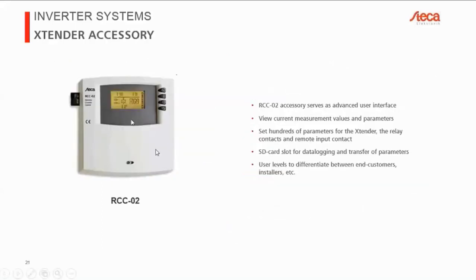So that's what the RCC02 is for. You can already sort of see it on the display. It shows you the current state. It shows you voltages, currents, powers, and temperature, all kinds of things. So you can use that as an advanced user interface. You can see all your current measurement values and parameters. Like I said, there's literally hundreds of parameters you can set on the Xtenders. In practice, you typically only need to set about 5 to 10 parameters, depending on your type of battery, mostly, and depending on your priorities, whether you want to prioritize the battery side or prioritize the AC input. That's up to you.